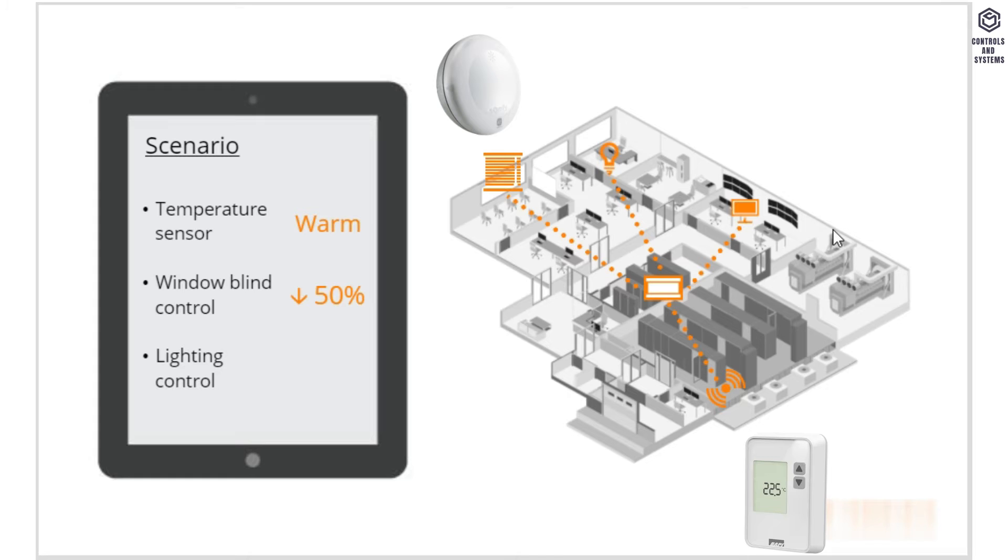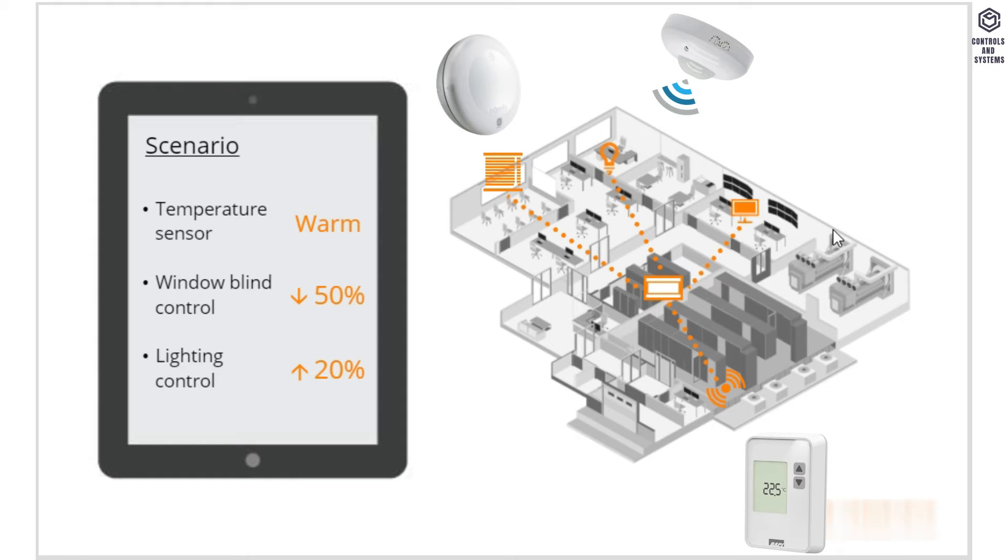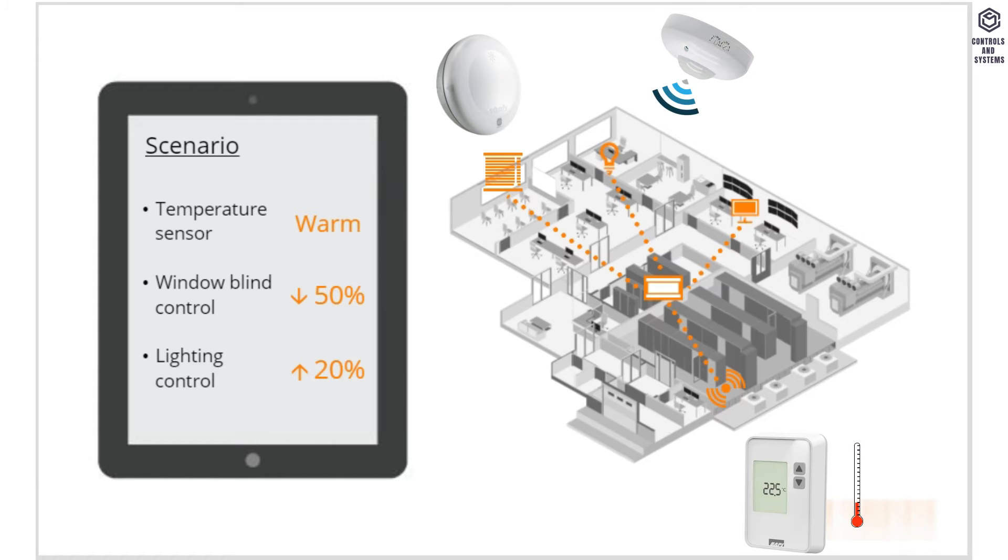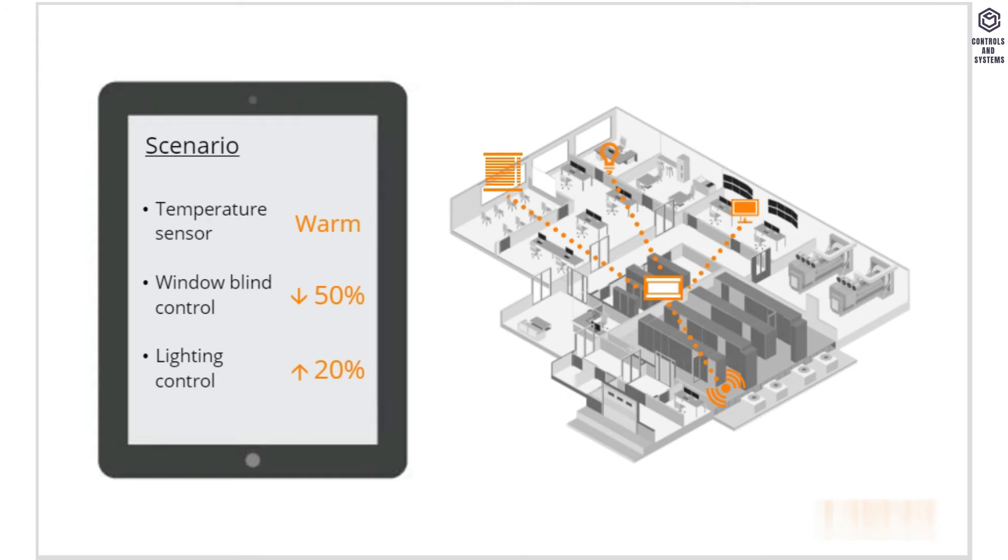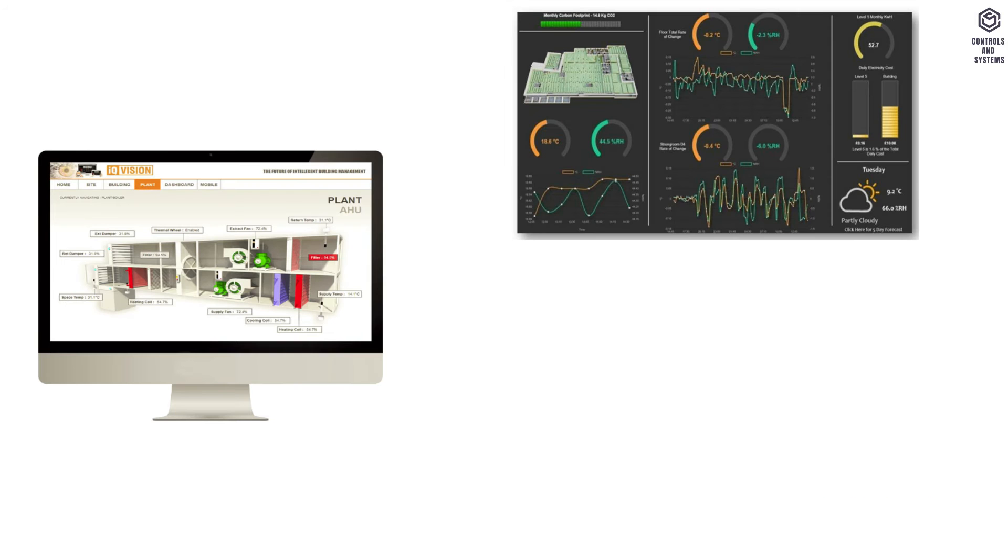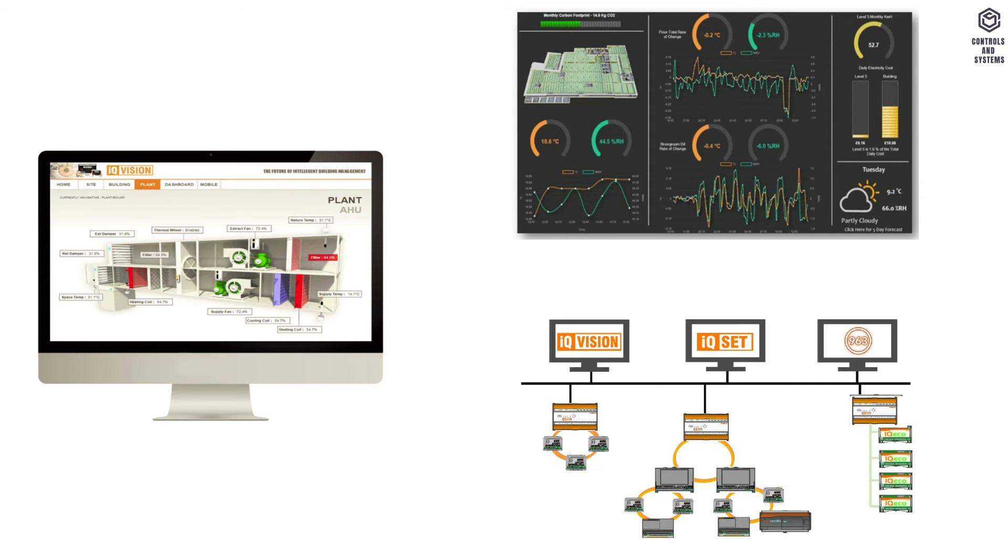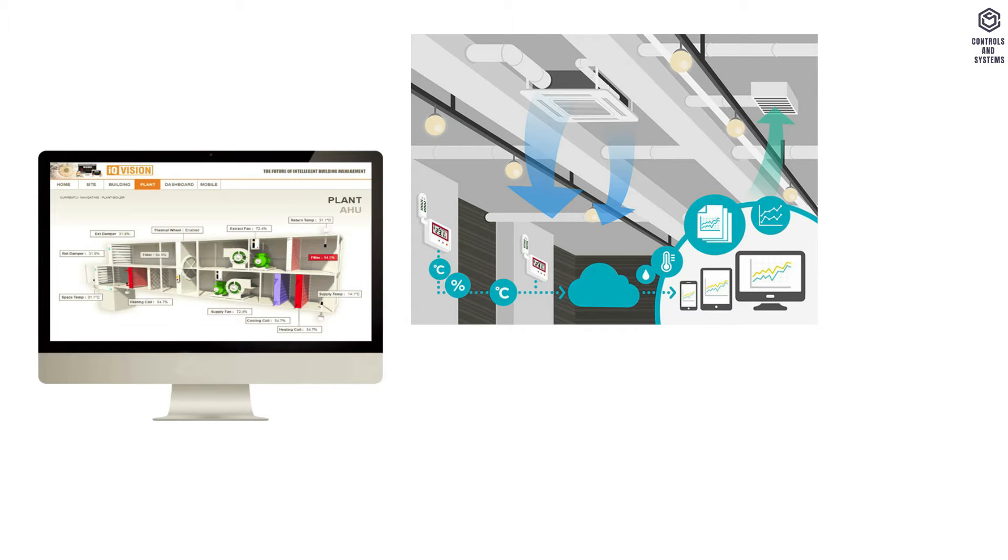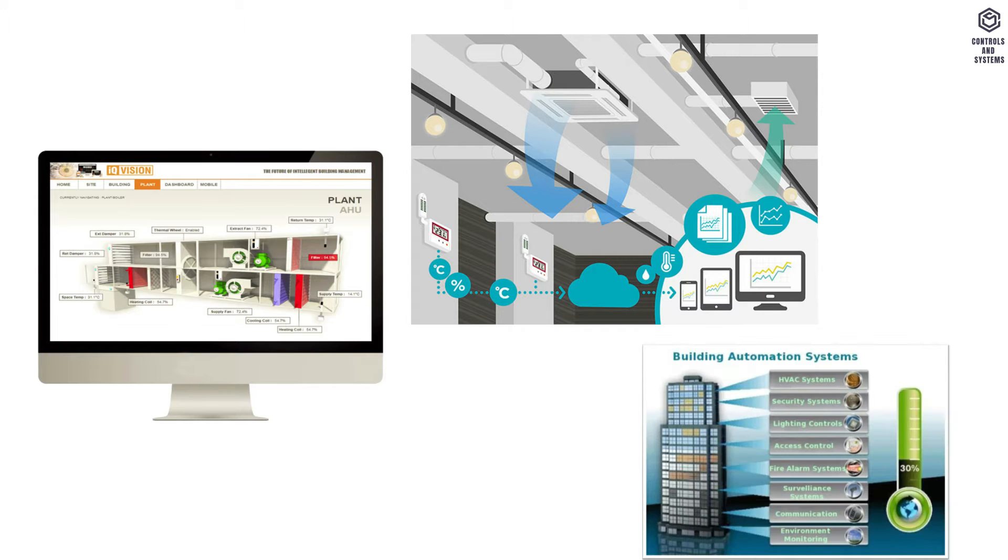The pre-configured strategy would alter the window blind to 50% coverage, reducing the temperature of the room. However, the strategy would also have to increase the lighting by 20% to ensure the room is bright enough to work in but not too bright that the temperature would increase again. The strategy makes sure that whatever information is received, an appropriate change is made in the system, taking other devices into account and acting accordingly. This makes sure that occupants are more comfortable and satisfied in their workplace. Due to the level of control, building efficiency is also maintained.